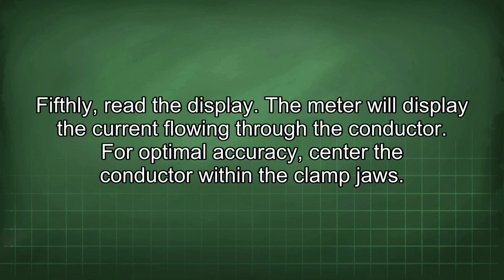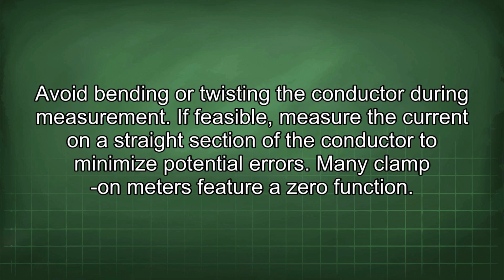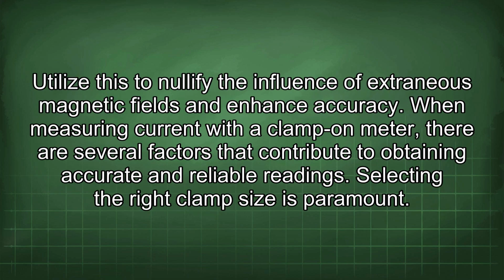For optimal accuracy, center the conductor within the clamp jaws. Avoid bending or twisting the conductor during measurement. If feasible, measure the current on a straight section of the conductor to minimize potential errors. Many clamp-on meters feature a zero function. Utilize this to nullify the influence of extraneous magnetic fields and enhance accuracy.